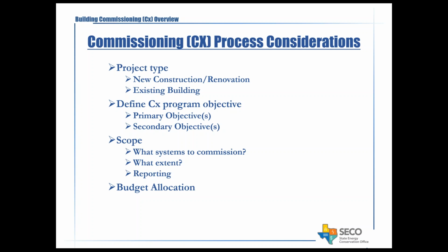Very important is to define the CX program. CX stands for Commissioning, and you need to define the program objectives: what is the primary objective, what is the secondary objective. The primary objectives could be energy saving and comfort improvement. The secondary objective could be ensuring that the maintenance and operations staff is up to speed on how to maintain these buildings if they're an integral part of the commissioning process. So you define those objectives.